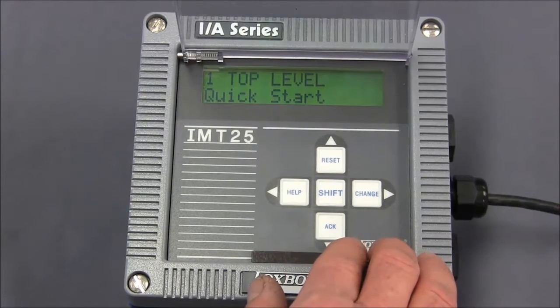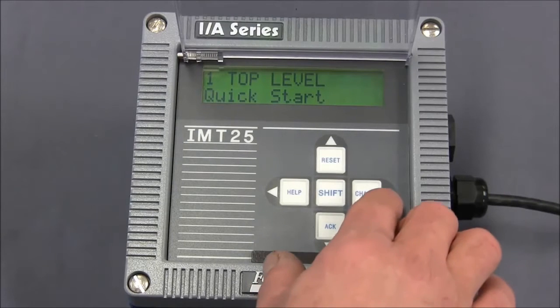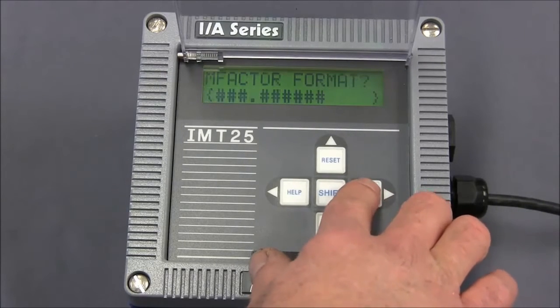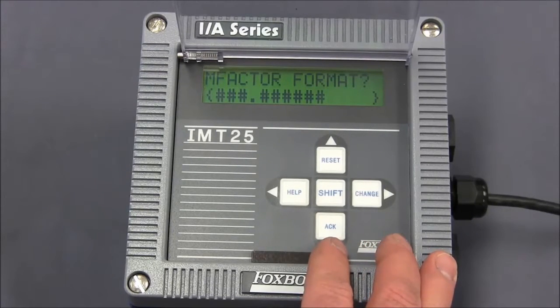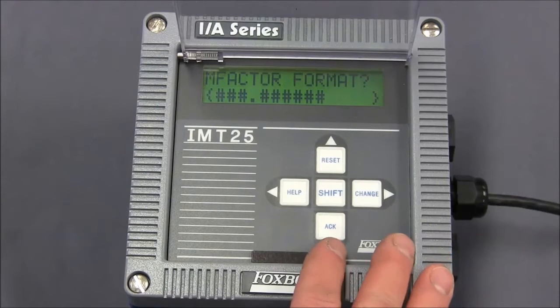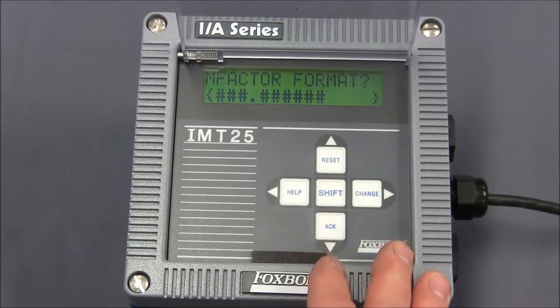Next, we'll enter into the quick start menu by pressing the change key or the right arrow key. The first thing that comes up is the meter factor format. Here, you can change the position of the decimal point depending on the calibration factor that's stamped on your flow tube.